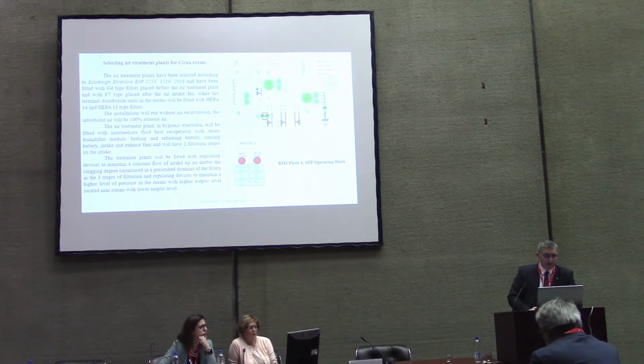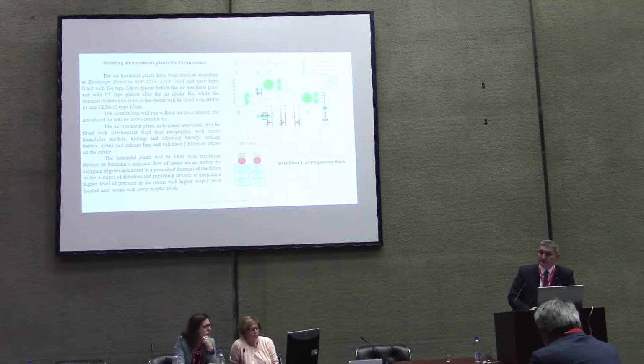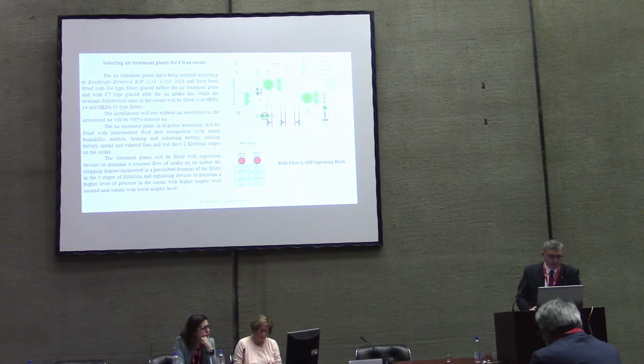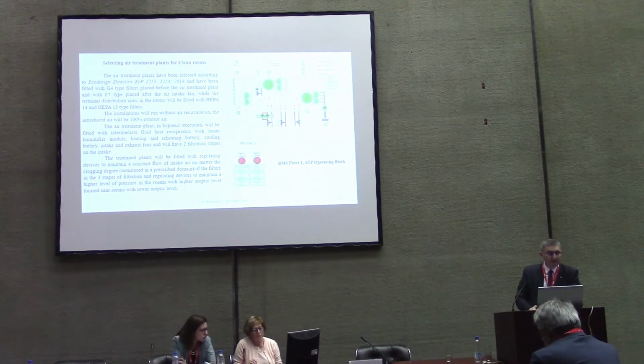The air treatment plant is of hygienic execution. It will be fitted with an intermediate fluid heat recuperator, with a steam humidifier module, heating and reheating battery, cooling battery, intake and exhaust fan. It will have 2 filtration stages of intake. Very important is the system of heat recovery with the intermediate fluid, special for the clean rooms.